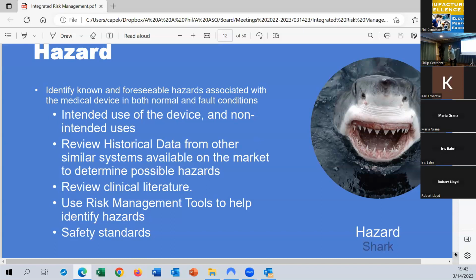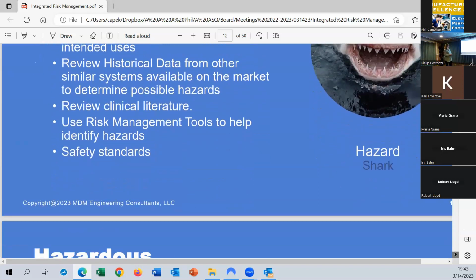In order to identify hazards, we need to know the intended use of the device and even possible non-intended uses, because sometimes people use things in ways they're not supposed to, and that can result in hazard. You want to look at historical data from other similar devices and try to learn from it, right? What caused issues with this device? You want to review clinical literature. You want to do things to identify hazards, like perform FMEAs, HAZOP, and hazard analysis. And a lot of times safety standards will tell you that for a particular thing, these are hazards that you have to be concerned with.